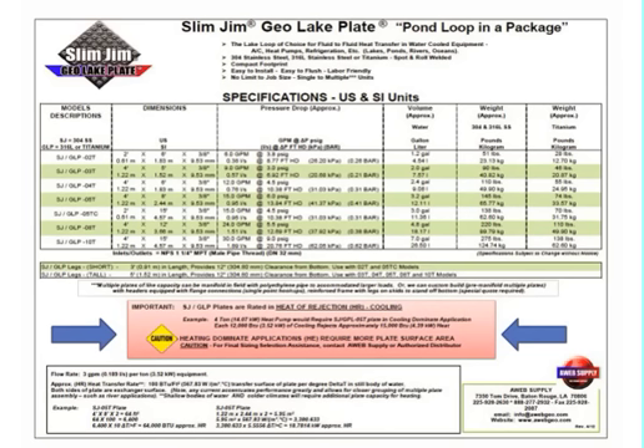Here is the Slim Jim. It's made down in Louisiana, AWeb Supply, and I emphasize this red highlighted box here where they even mention that you need to work with them. You need to contact them if you're going to a heating dominant application, in a chilled water environment. So make sure that you do that. Just don't go to their website and order that size for a 5-ton heat pump if you're in the northern climate, because you're going to be undersized if you take one just off their website and apply it to your heating dominant load needs. So please make sure you do that. They're great heat exchangers, I have no qualms with them. I just want to make sure that everybody has the right size for the application.